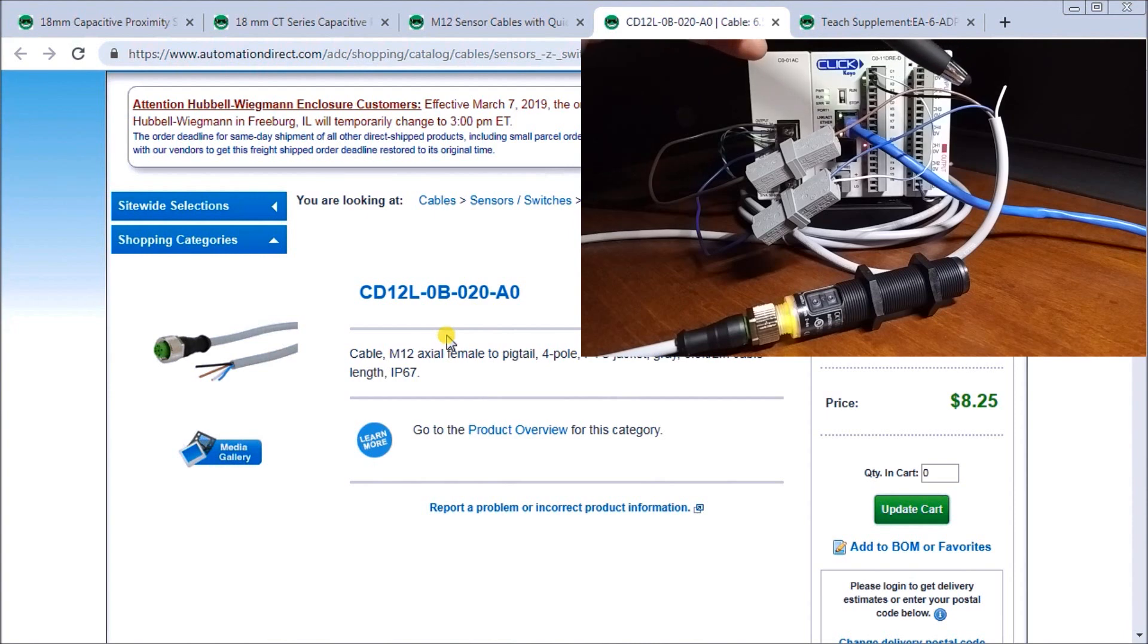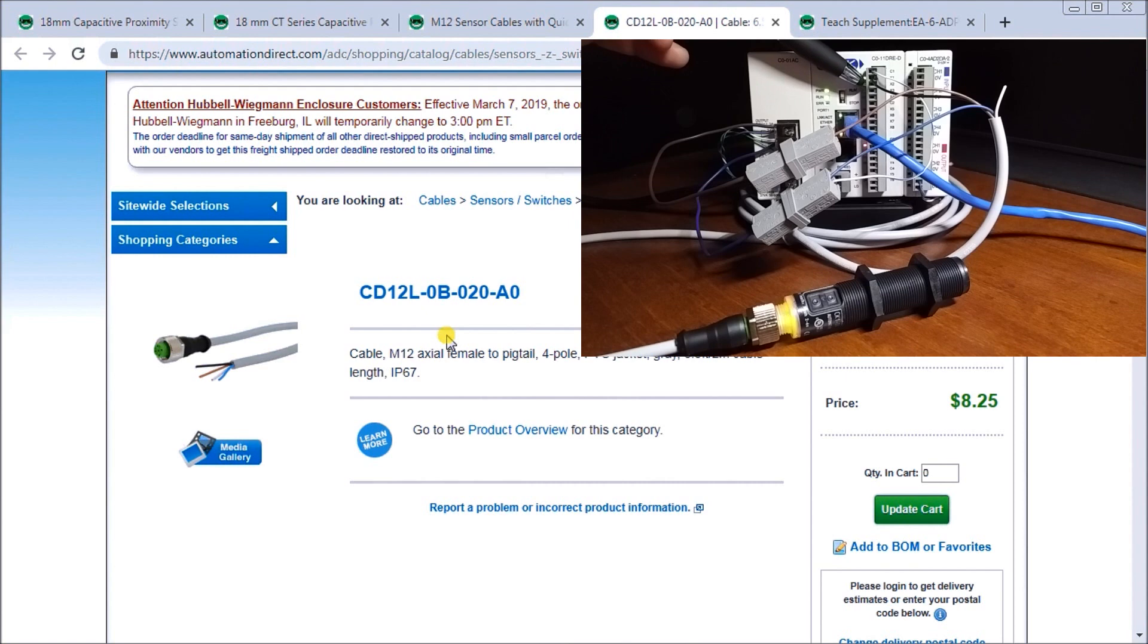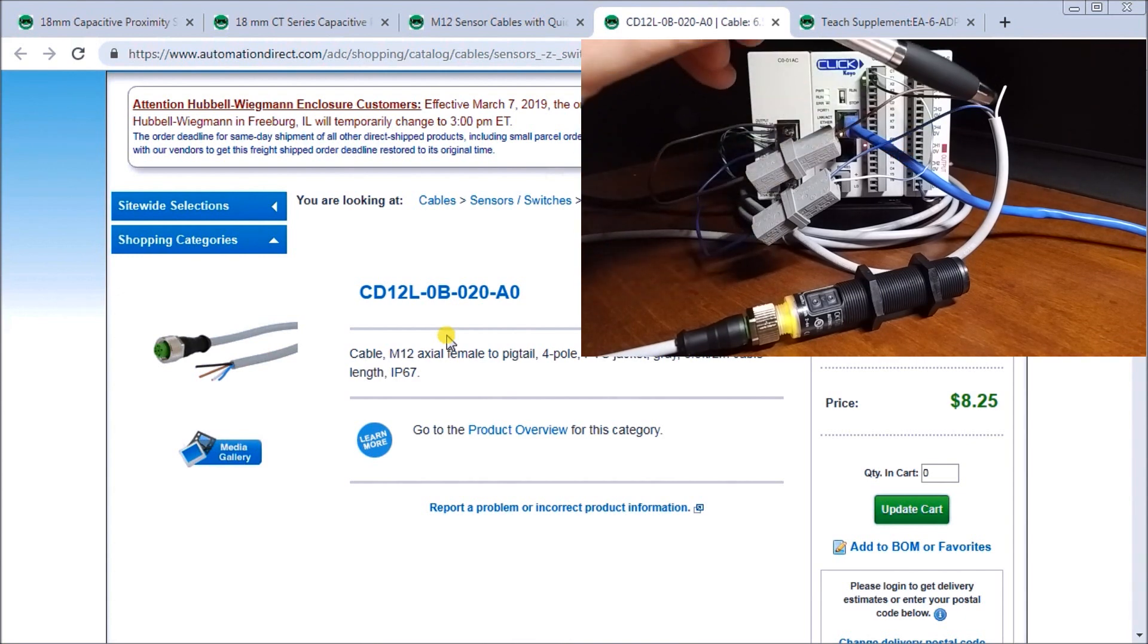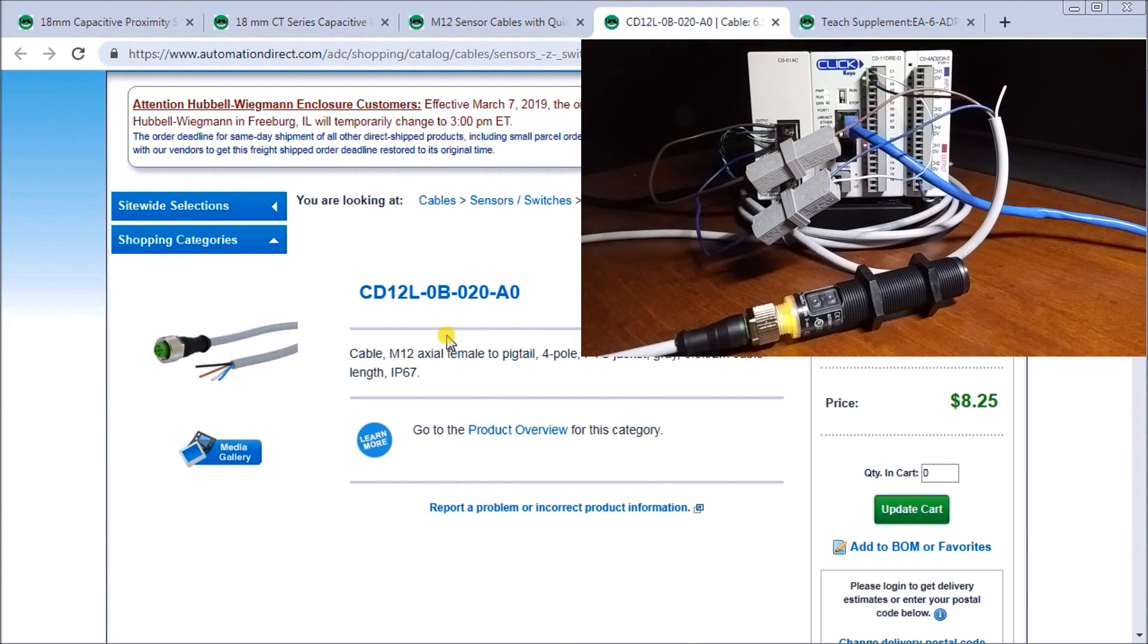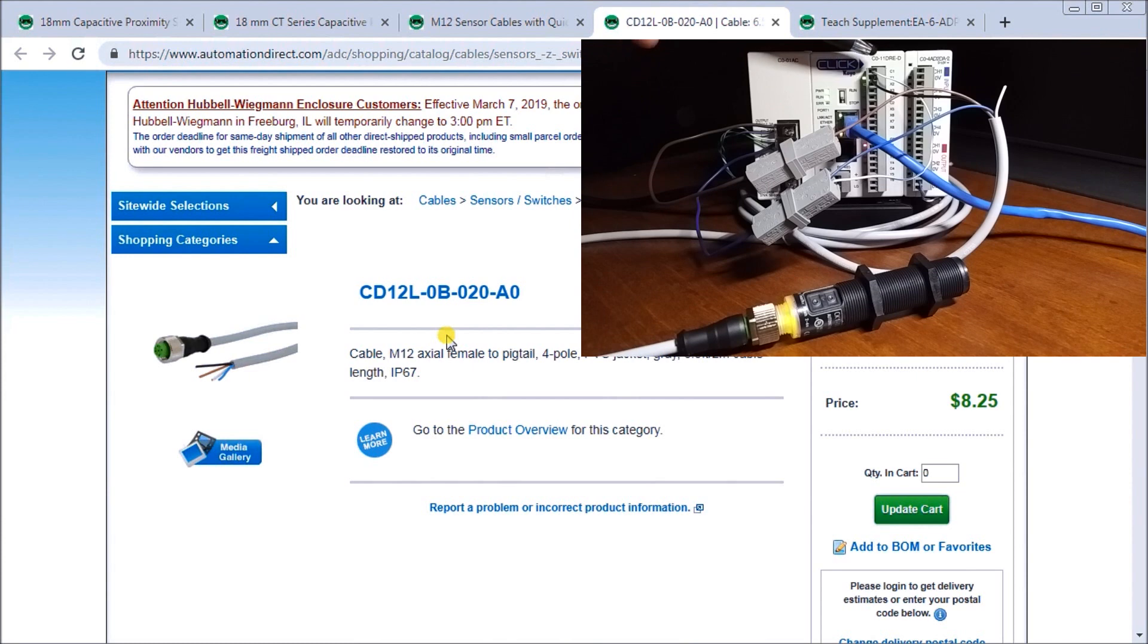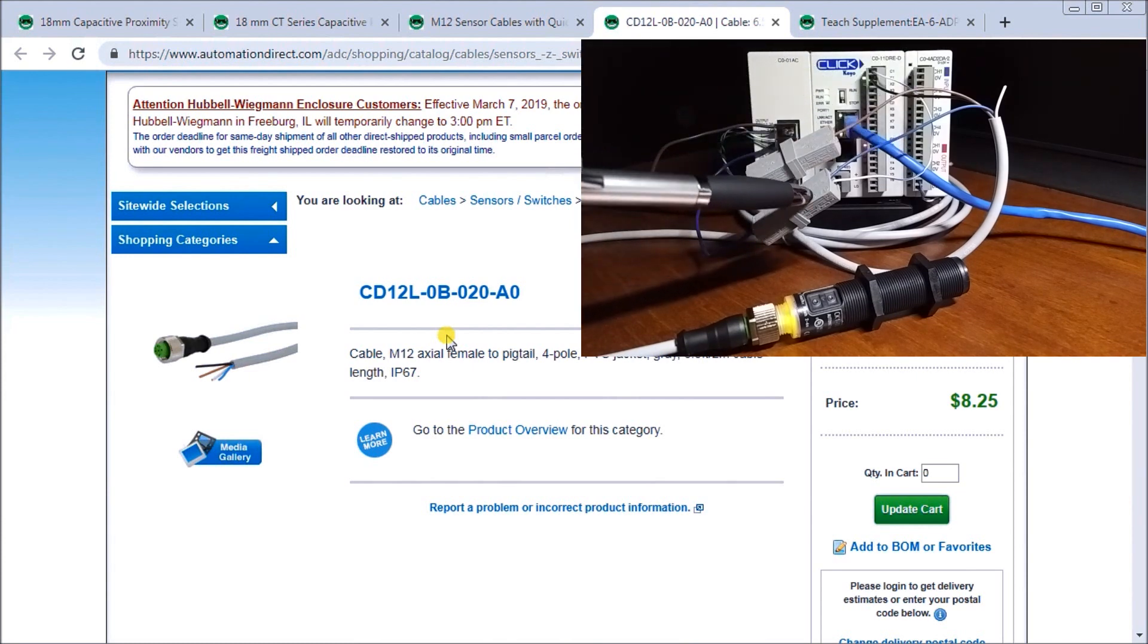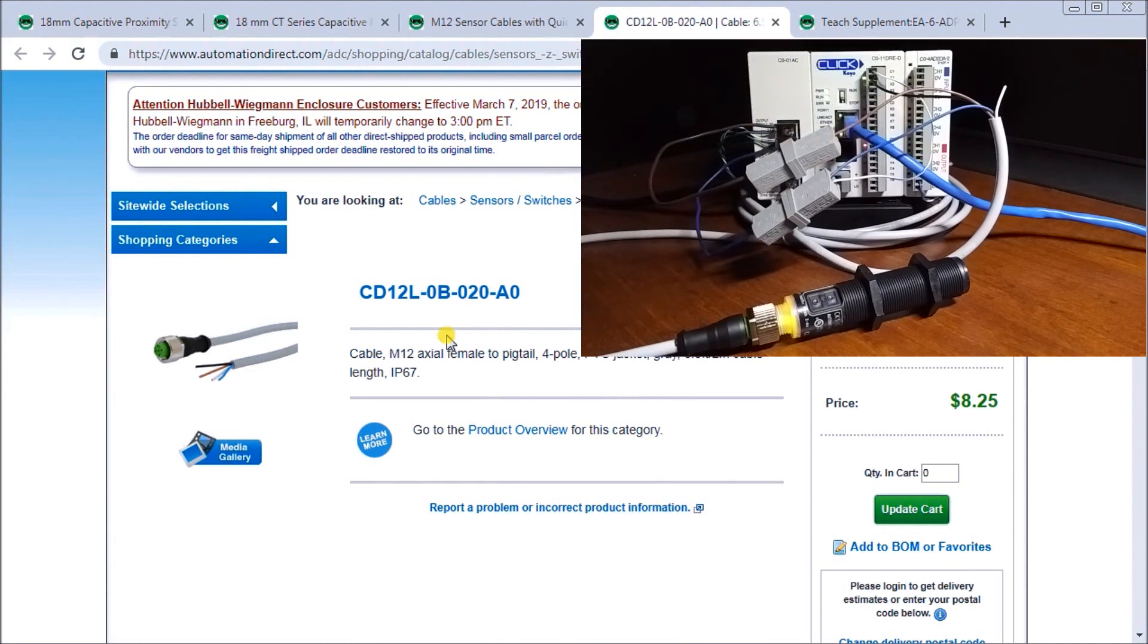We have a black wire which is our switching wire which goes into our actual input. Then we also have our brown wire which is our plus voltage. We have a blue wire which comes back which is our zero volts DC. And then we have our common for input which is our white blue in our case here and we're going right now to the zero volt DC.